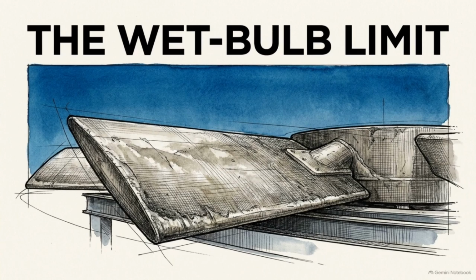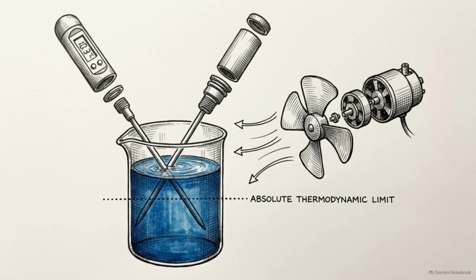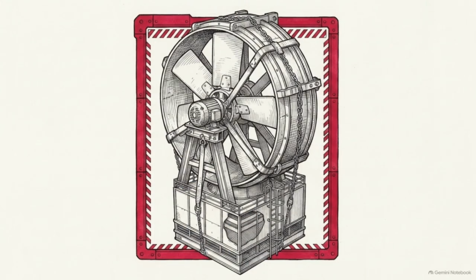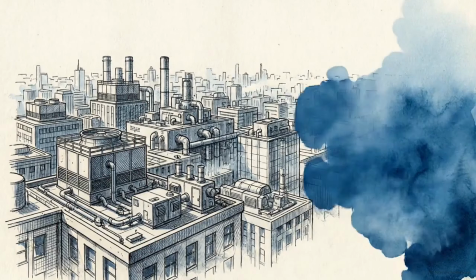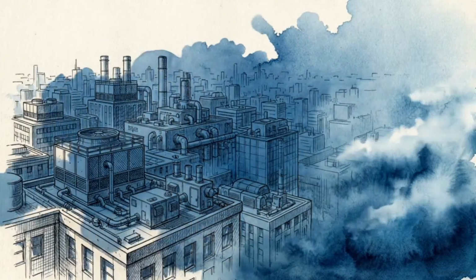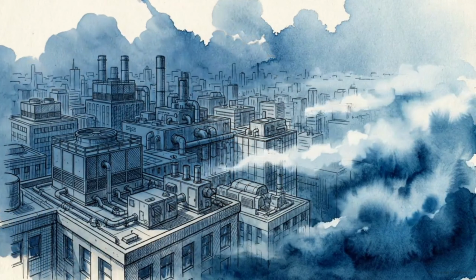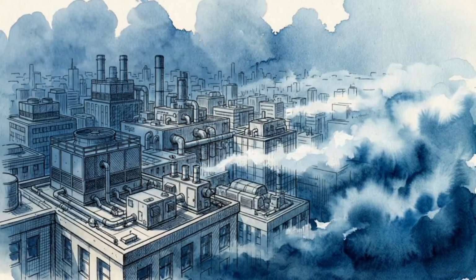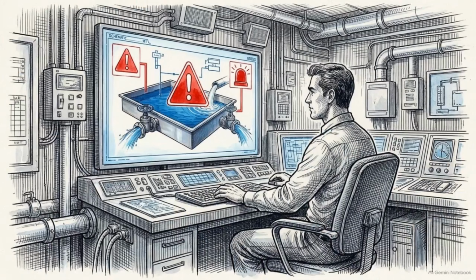This reveals an unbreakable law of thermodynamics. A cooling tower can never cool water below the ambient wet bulb temperature. You could double the size of the fan, and that limit remains absolute. While a smaller approach signifies a highly optimized, efficient tower, the entire central plant's efficiency is ultimately capped by the local climate's humidity. This continuous evaporation process introduces a severe, ongoing mass balance problem for plant operators.